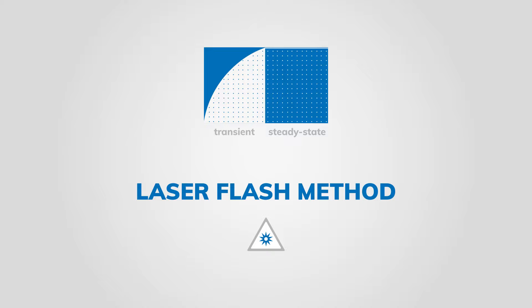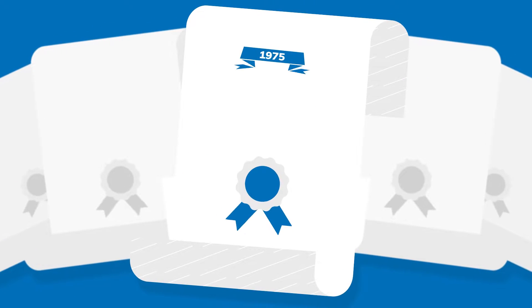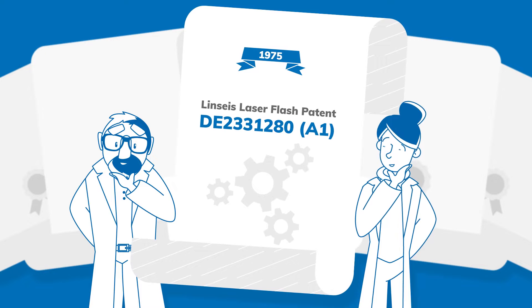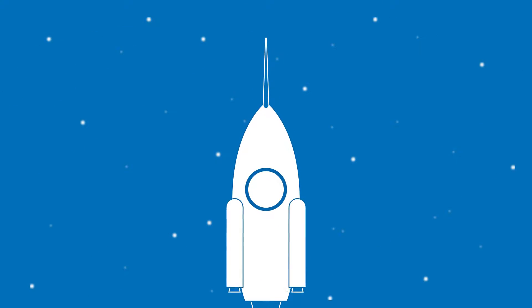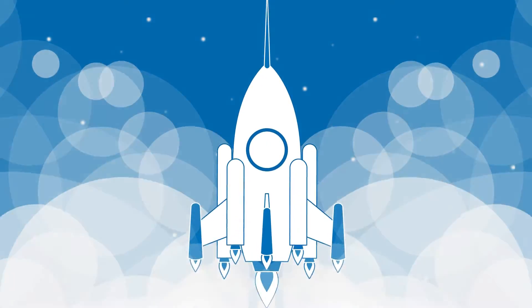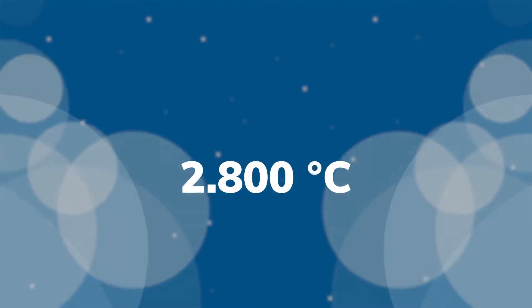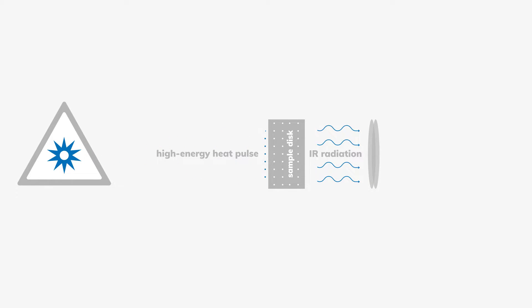The laser flash method is a transient measurement method based on a patent from 1975. Despite its high cost and complexity, it is still widely used today, and for a good reason. With the laser flash method, materials can be tested automatically even at extreme temperatures of up to 2,800 degrees Celsius. The sample disk is exposed on one side to a short, high-energy heat pulse from a laser or flash lamp. The resulting temperature rise on the opposite side is recorded with an infrared detector. In relation to the sample thickness, the thermal diffusivity can thus be calculated using a mathematical thermal conductivity model.